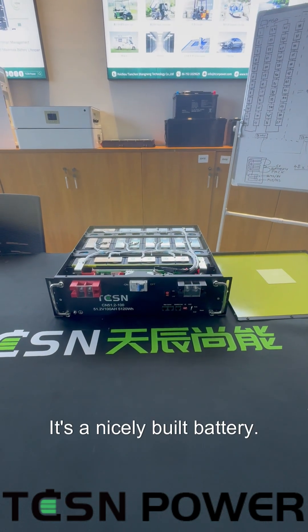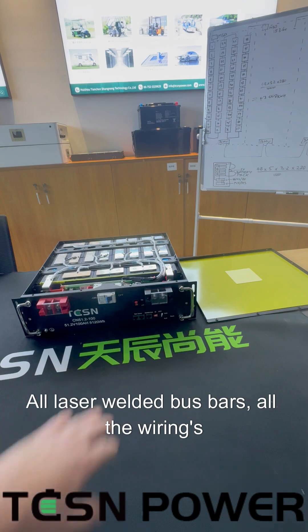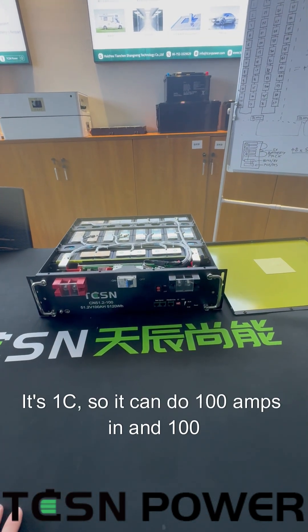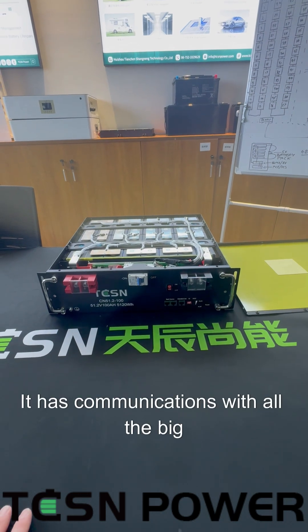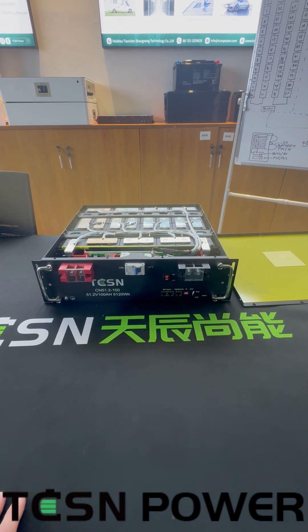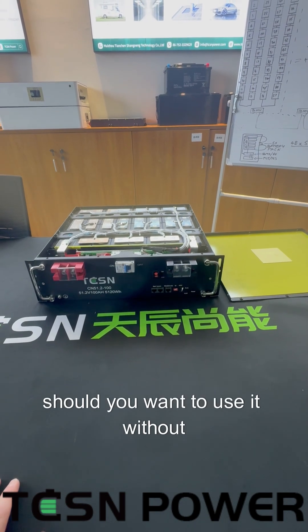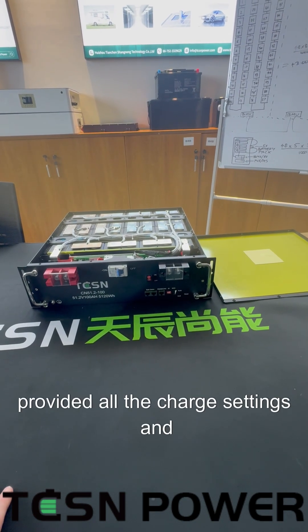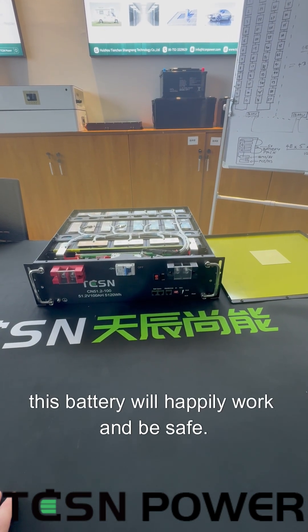It's a nicely built battery — all laser welded bus bars, all the wiring is done really nicely. It's got a very good BMS. It's 1C, so I can do 100 amps in and 100 amps out. It has communications with all the big brand inverters such as Victron and Deye. It also works happily as a self-managed battery, so should you want to use it without communications, provided all the charge settings and voltages are correct, this battery will happily work and be safe.